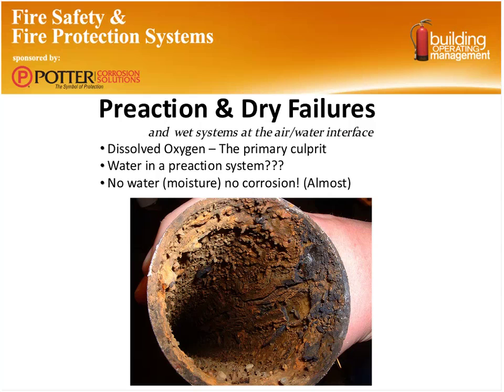As an industry, we're starting to learn more about it. In some cases, we're also starting to see it in pre-action and dry systems. And that can really baffle people, because they think, well, I don't have any water. How could I have anything eating away at my pipe in a pre-action or dry system? Well, the reality is pre-action and dry systems are never truly dry. There's always some kind of an air-water interface in those. There's a little bit of moisture left in.